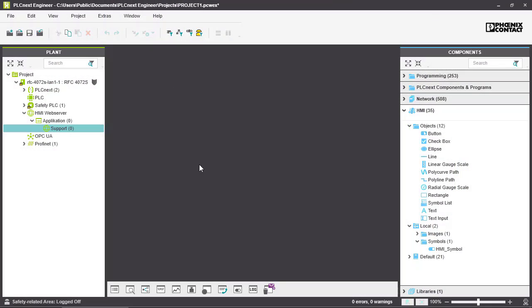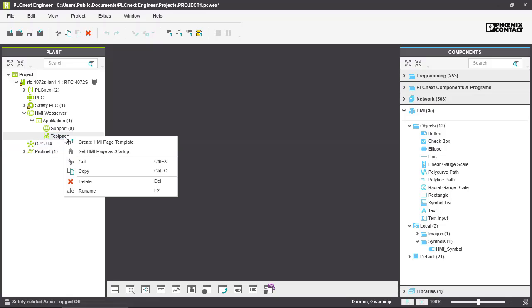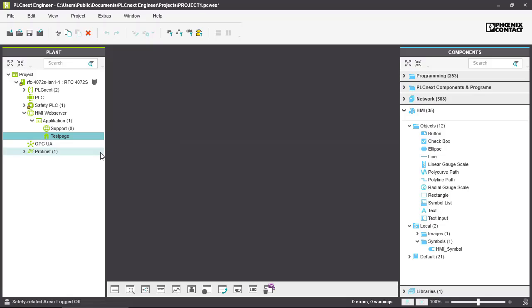To use the HMI visualization, we first have to create an HMI page. On the left side in the plant section, under the project folder HMI web server, right-click on application and select 'Add HMI page'. Give it a name — let's say 'test page'. If you have more than one HMI page, an error will occur if you have not selected a starting page. Fix this by right-clicking your desired page and setting it as the HMI startup page, and the error will disappear.